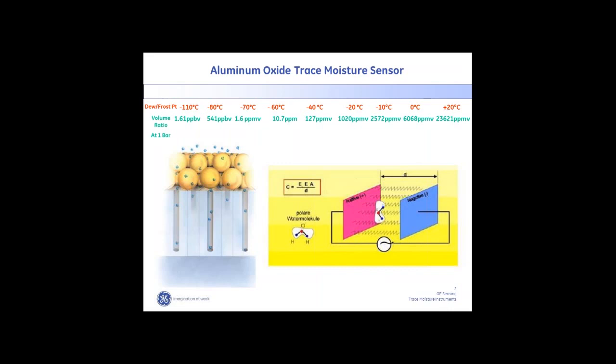The way this sensor works is that you have a matrix that absorbs water in the vapor phase, and that matrix acts like a capacitor. Water itself is a polar molecule — it has a positive side and a negative side. As water gets into the capacitance field, it changes the capacitance. Our sensor is structured to essentially count the charge density, and that is directly related to the concentration of water surrounding it.